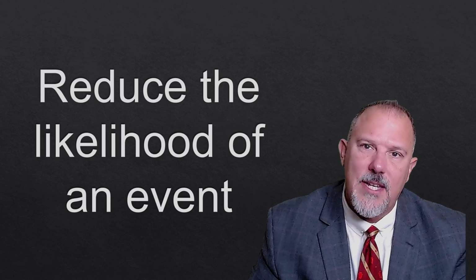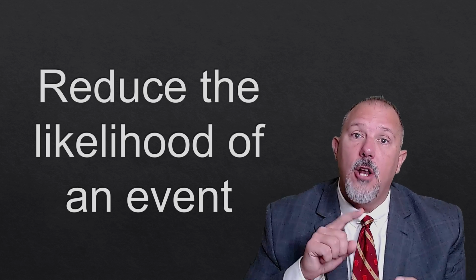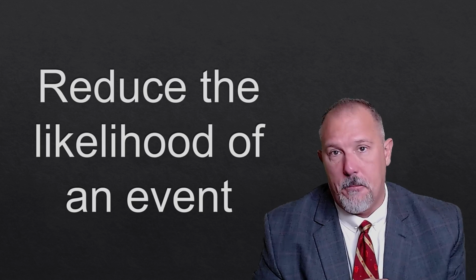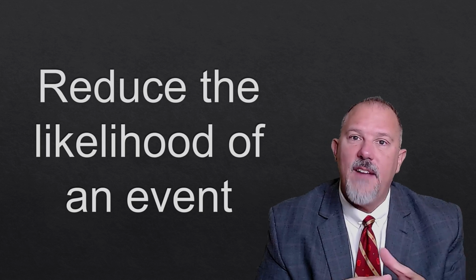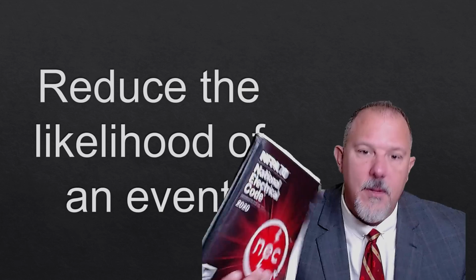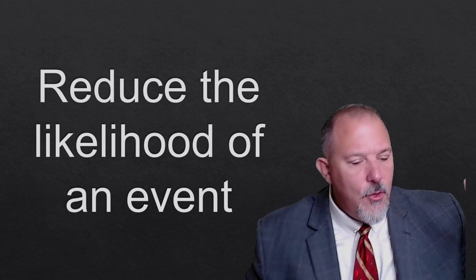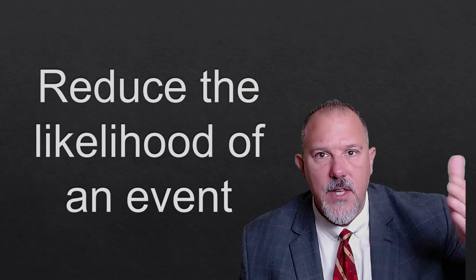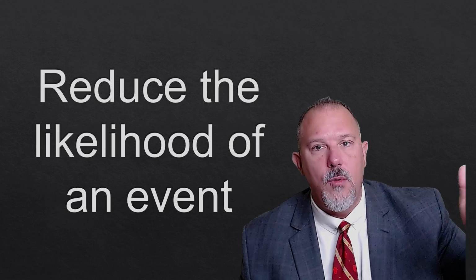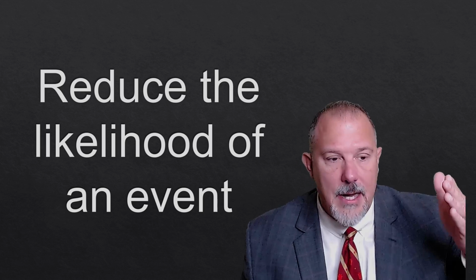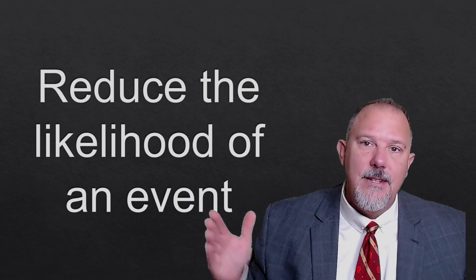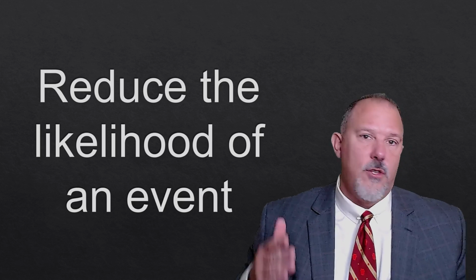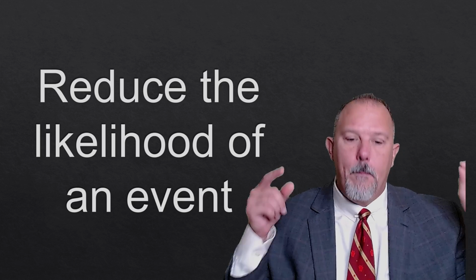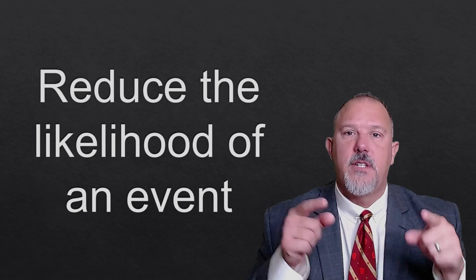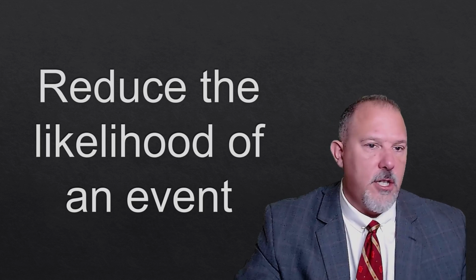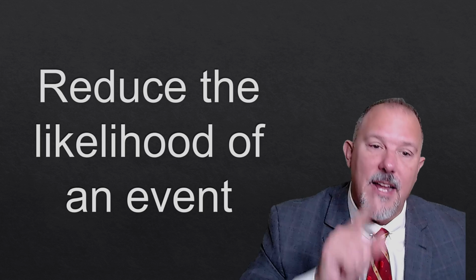So any place where you see disconnect requirements and lock requirements for lockout tagout purposes, you don't have to just do the bare minimum that's in this document. You can put in a disconnect if you know that someone who's going to be working on that equipment is going to need to hunt and peck to find an overcurrent device to open or a switch to open. Put one there. Help them facilitate an electrically safe work condition. Help them reduce the likelihood of an event.